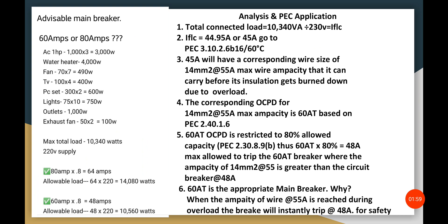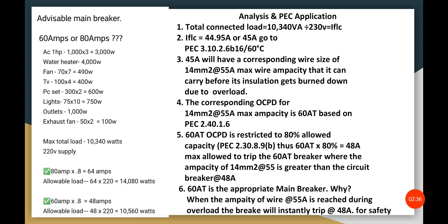The colleague also had this computation: 80 amperes times 80 percent gives 64 amperes, and a level maximum load of 14,080. For the 60-ampere breaker, 60 times 0.8 as per PEC gives 48 amperes, and the load schedule level is 10,560 watts. Let's do the analysis and PEC interpretation of this inquiry to find the correct answer.